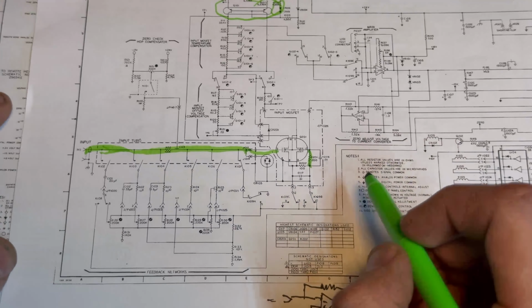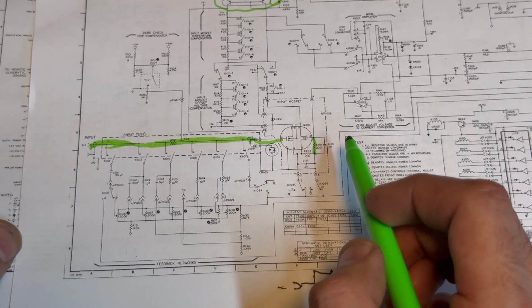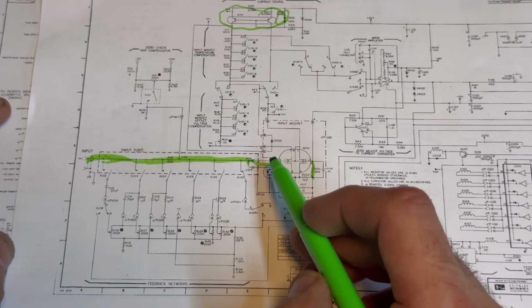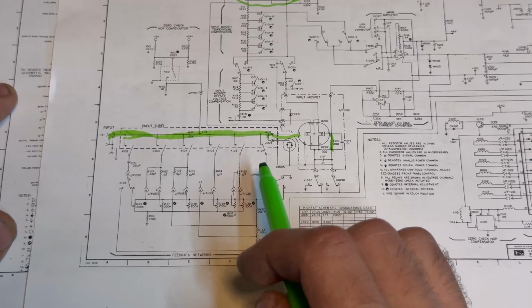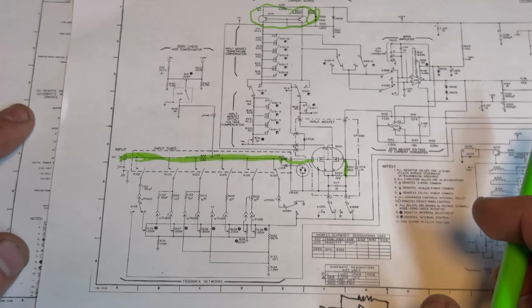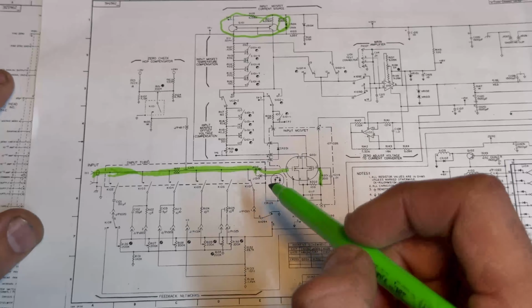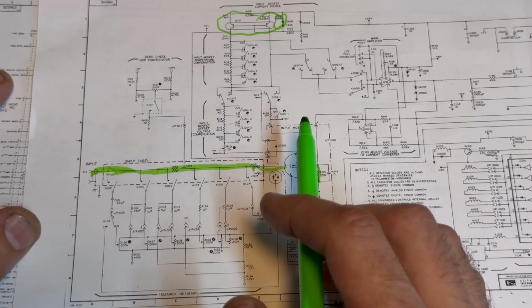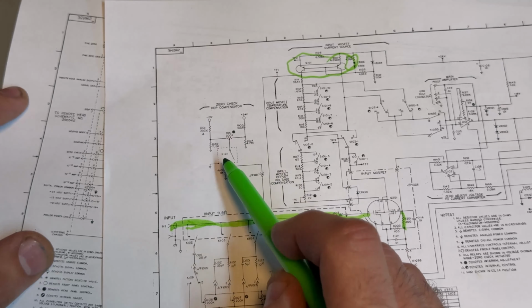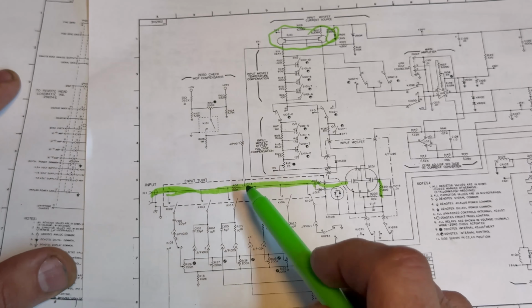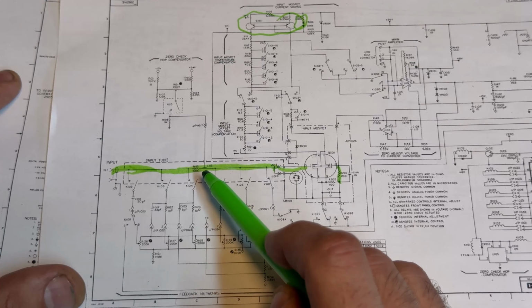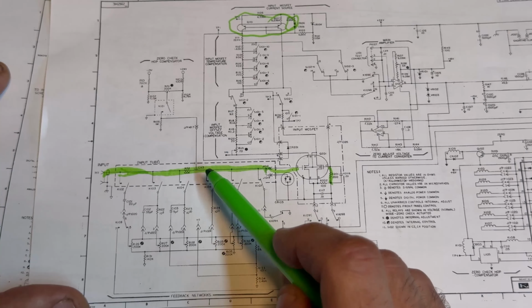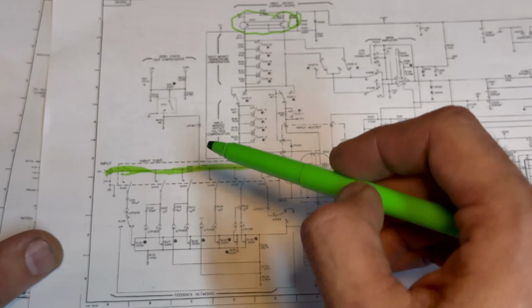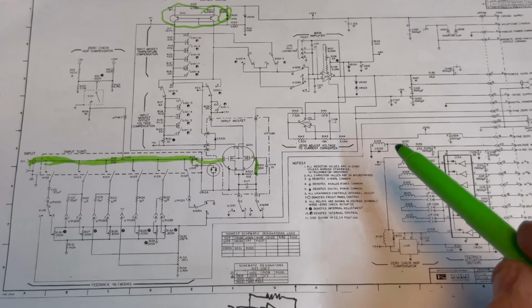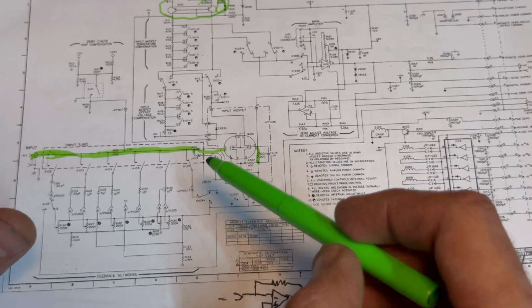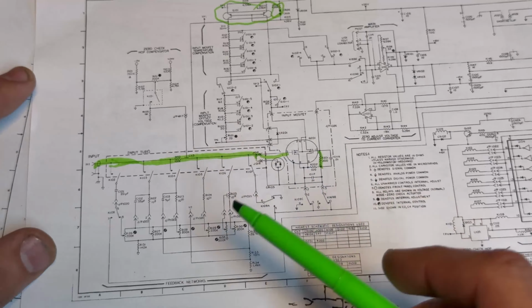So when you enable zero check, it basically shorts the input to ground. And when you do that, you inject some charge. Any actuation of a switch injects some parasitic charge into the electrometer. So what happens is when you disable the zero check, first it disables the switch here, and after a very, very short amount of time, a relay disengages as well here to extract that charge. And you can see there's a sort of a feed-through symbol here. It's just a patch of conductor wrapped around the center conductor here that extracts that remaining bit of charge. So when you're setting it to and from zero check, you don't inject or subtract unwanted charge.